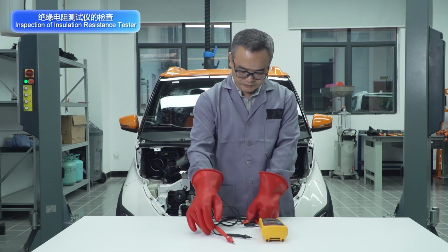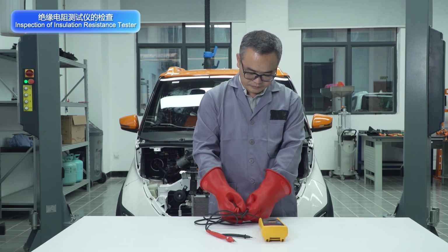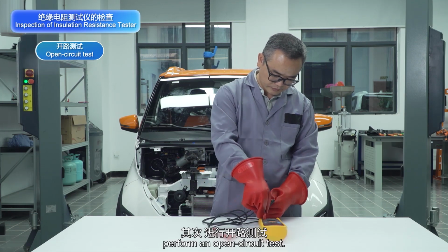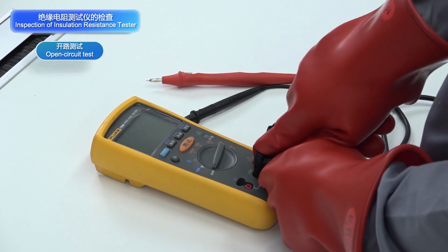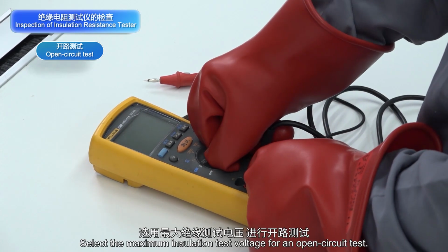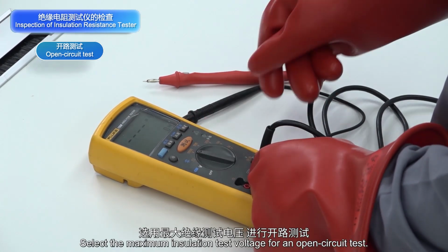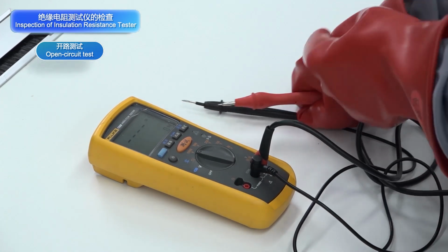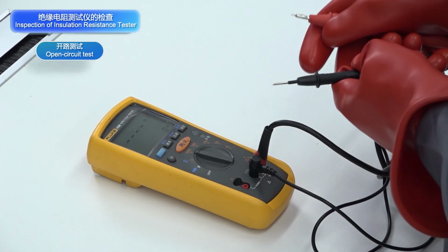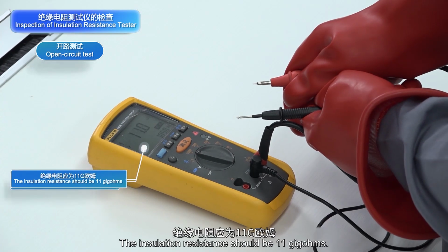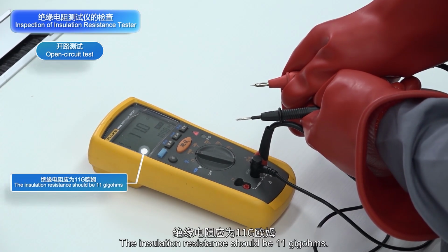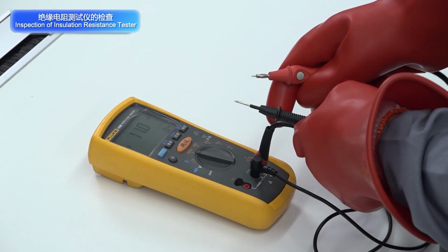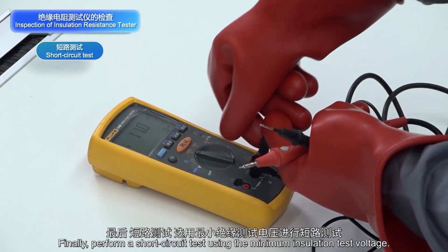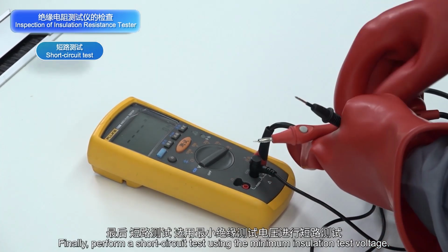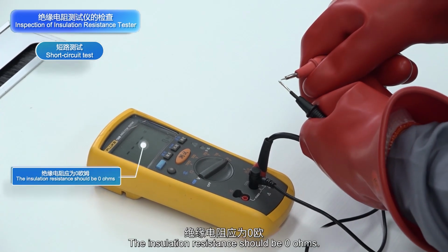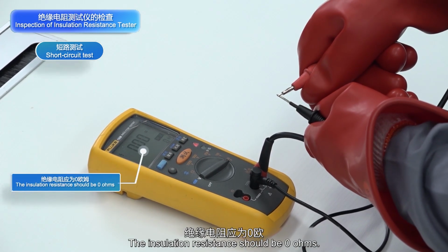Secondly, perform an open circuit test. Select the maximum insulation test voltage for an open circuit test. The insulation resistance should be 11 gigohms. Finally, perform a short circuit test using the minimum insulation test voltage. The insulation resistance should be 0 ohms.